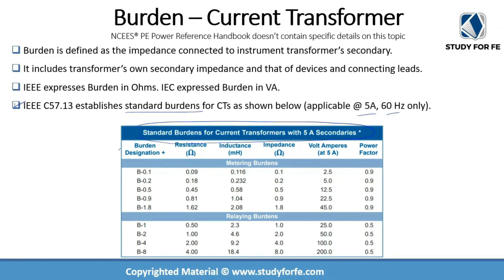Burden is designated, according to IEEE, as B-a number for current transformers. There are two different categories of burdens: metering burden and relaying burden. B-0.1 means the total impedance is 0.1 ohms. Similarly, B-1.8 means the maximum allowable burden is 1.8 ohms. For relaying burdens, you have B-2, B-4, B-8, and so on — representing 2 ohms, 4 ohms, 8 ohms, and so on.